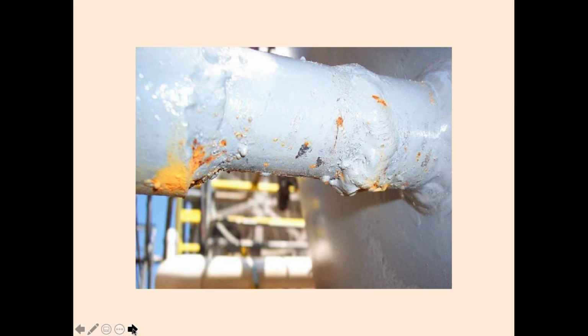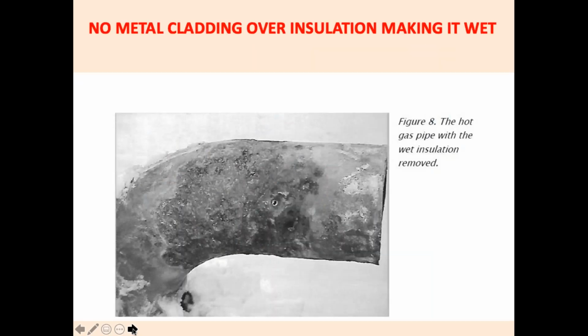Improper, as I mentioned, not using long stem valves. You can see the valve, which is a very small valve, and the accident has taken place. Total pipe is internally rusted. So it is very important how to do the proper insulation, proper pipe, proper anti-rust painting of the piping, etc.